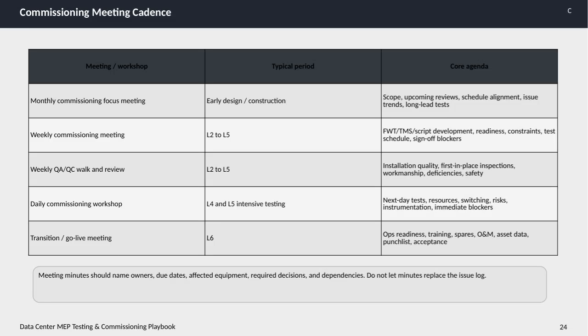Here, we have the commissioning meeting cadence, which outlines the different types of meetings and workshops essential throughout the data center commissioning process. Starting with the monthly commissioning focus meeting held during early design and construction phases. These sessions cover overall scope, upcoming reviews, schedule alignment, trends and issues, and planning for long lead tests. Next, the weekly commissioning meetings take place from Level 2 to Level 5.